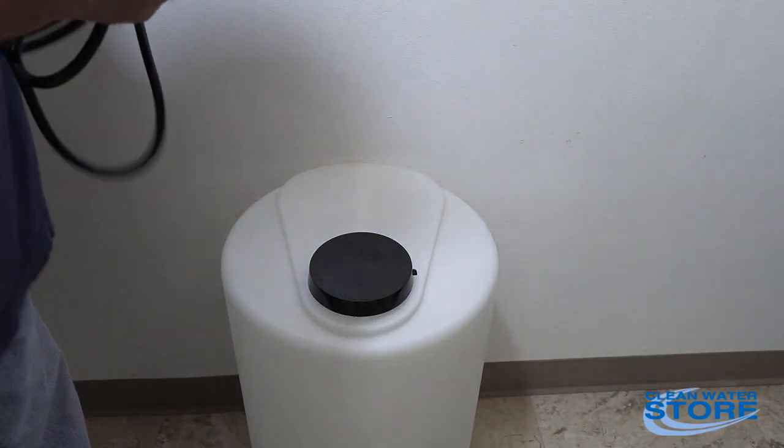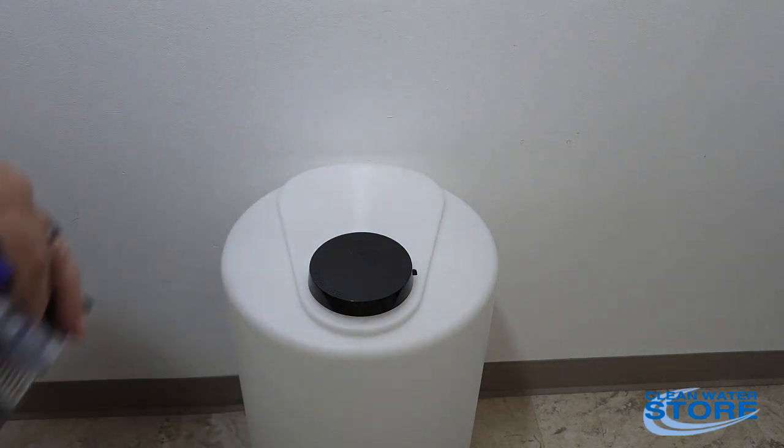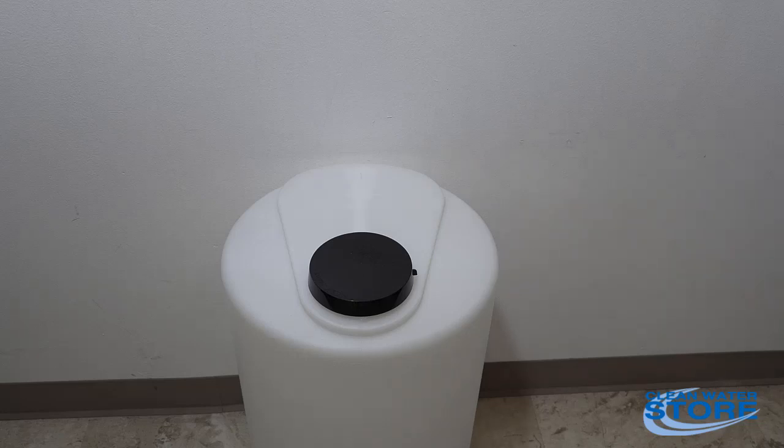The first thing we're going to do is mount the pump. We recommend mounting these pumps directly on top of the tank. The shortest distance for that suction hose coming up is better to keep your prime. You can put it on a shelf above, but you don't want it higher than 60 inches above the tank.